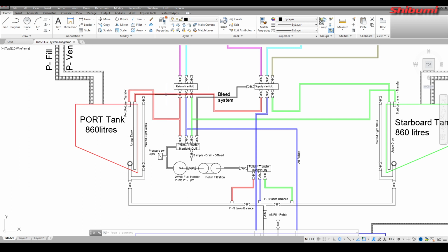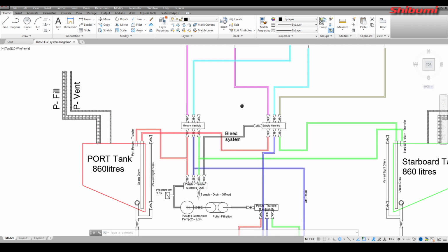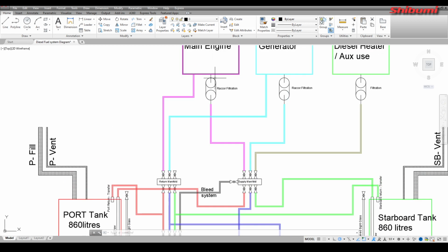So say if there was air in this hose here, once I put the pressure on, it'll blow fuel all the way back down this line and the bubbles will be heard coming out of the tank. And it'll fill that tank so it's solid diesel. Turn off that, then say turn on the engine, and then send pressurized diesel all the way to the filter. So if I've changed the filters or need to change the main filter on the engine, then I can open the bleed screw and it'll let out the air.